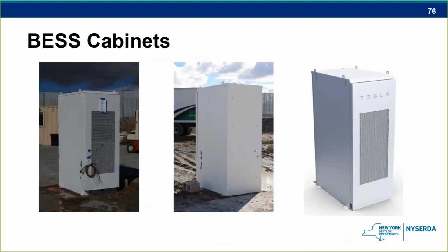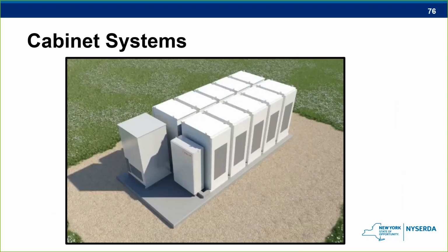This here is an example of battery energy storage system cabinets that house batteries and can be installed outdoors. These are maybe somewhere in the ballpark of the size of a refrigerator. And this here is an example of an entire outdoor cabinet system. And this is kind of a nice example showing how the size and separation requirement that we talked about earlier is not required when a system is considered remote. There's definitely not 3 feet between each of those cabinets.